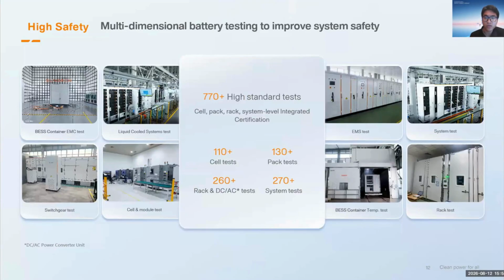And to validate the safety performance of the system in real applications, we conducted more than 770 high-standard tests covering the cell, pack, rack, PCS, and the full system, such as nail penetration test for the cell, some high temperature tests, EMS test, and liquid cooling system test. During this safety testing, we can ensure the reliable operation of the system.